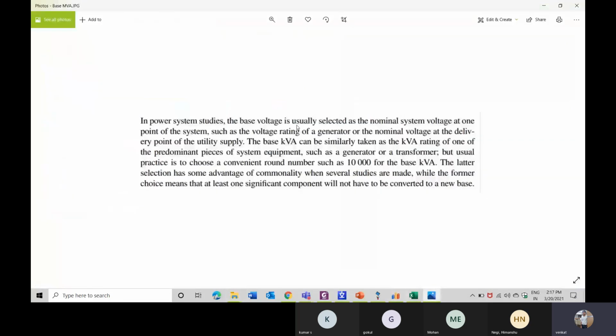In power system studies, the base voltage is usually selected as the nominal system voltage at one point of the system, such as the voltage rating of the generator or the nominal voltage of the delivery point at the utility supply. This is what we have seen up to now - like line to line voltage we said, this is the point they have called nominal voltage. Then they come to the base MVA - here they have called it base KVA.